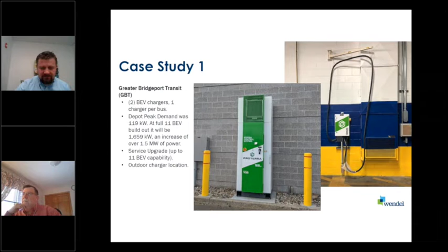is showing the impacts of what this project has caused on the power distribution system. Here's a single line diagram of electrical equipment prior to modifications. Pretty typical for bus maintenance facilities. It consisted of 1200 amp switchgear and a 500 kVA pad mounted transformer. So looking at the equipment, we determined that it was not large enough and would need to be changed out or replaced to accommodate the addition of the chargers.